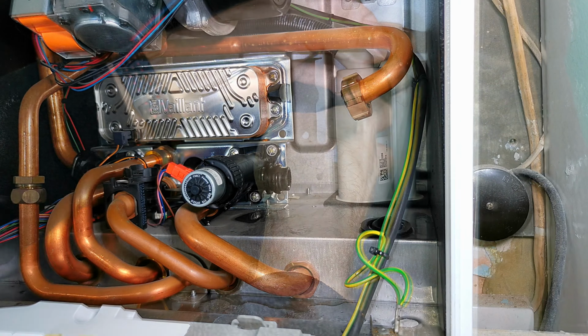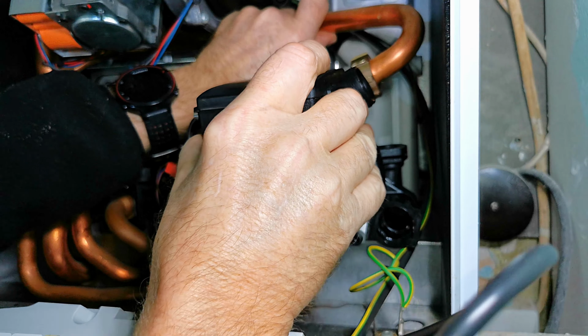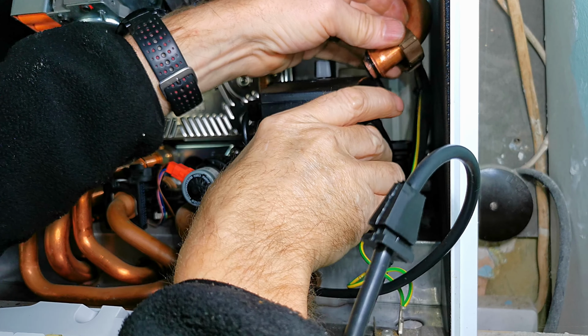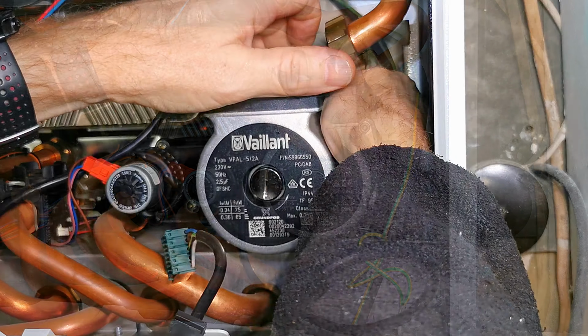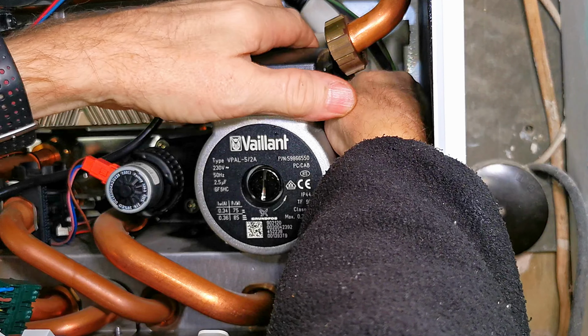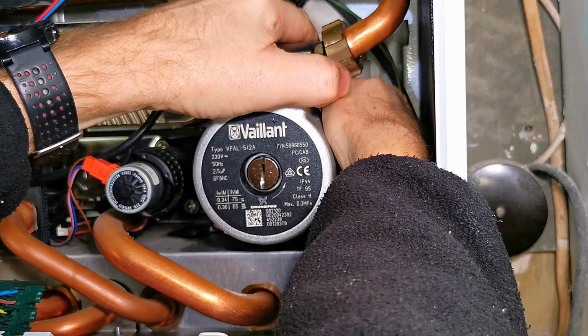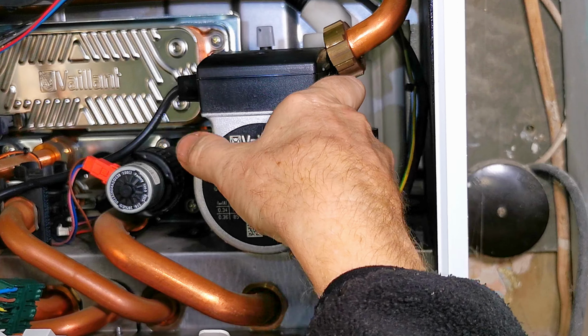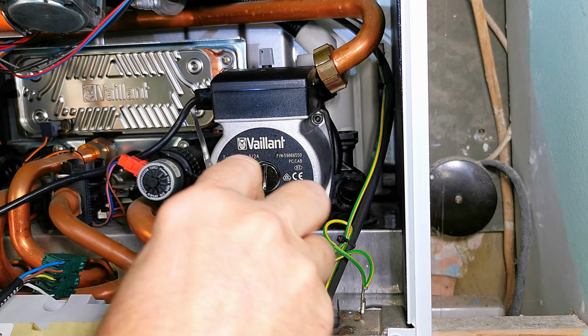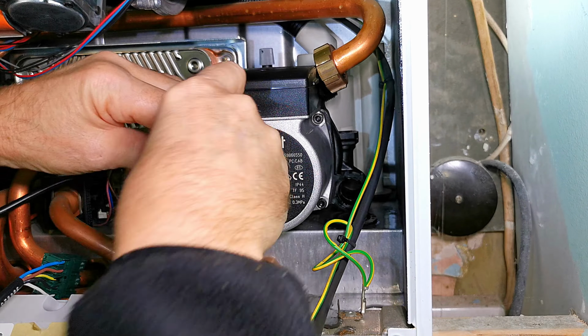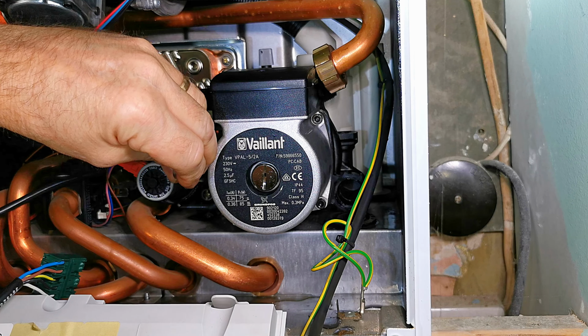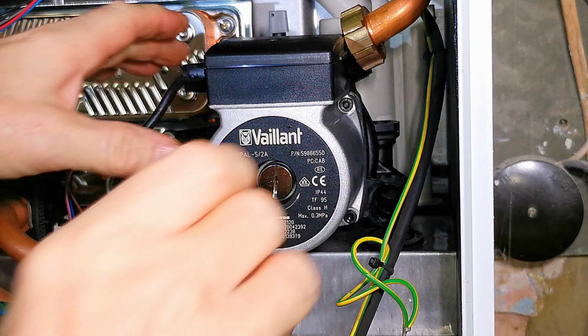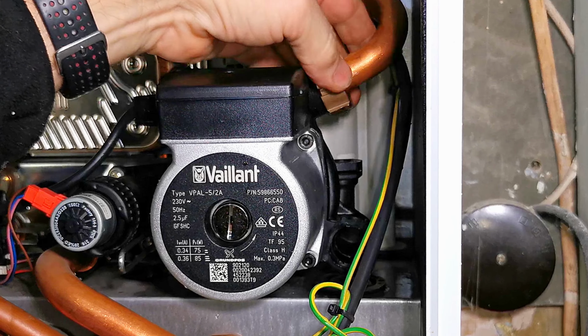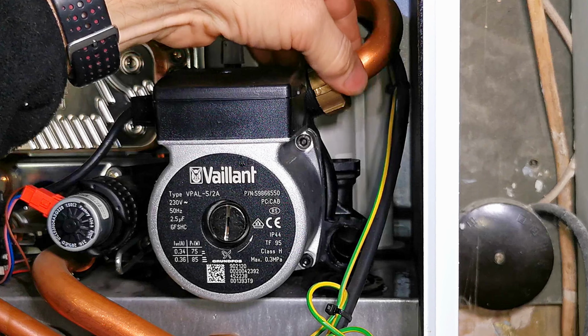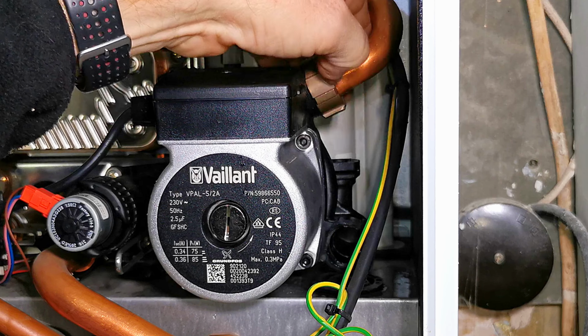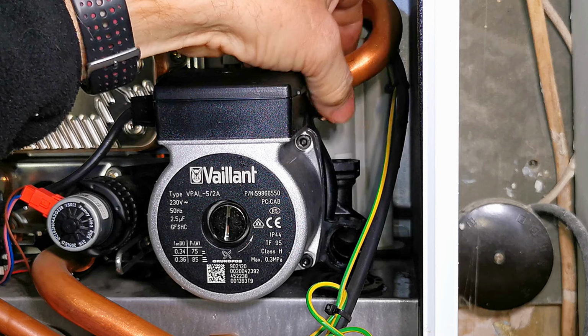And there we go. I now take the new pump assembly and put it in position in the boiler, locating it onto the diverter valve. I need to use 2 hands to do this because it's quite hard to push the pump across and onto that O-ring. But that's it, it's now on the O-ring. I'm now going to take the retaining clip, slide it into place so it locks the pump in its correct position. And there we go, that's now in the correct position. And the pump is nice and solid. I can now fit the return pipe and do up that nut. I'm always very careful with this nut because it's going onto a plastic screw thread.